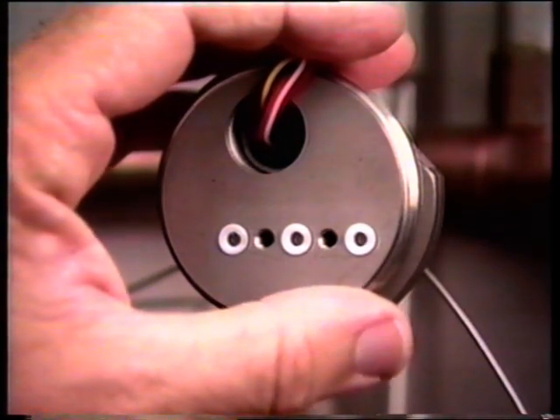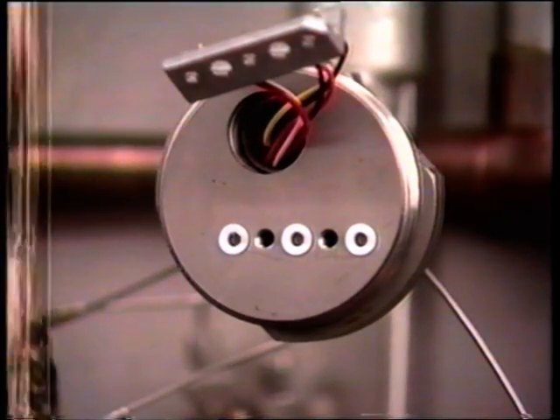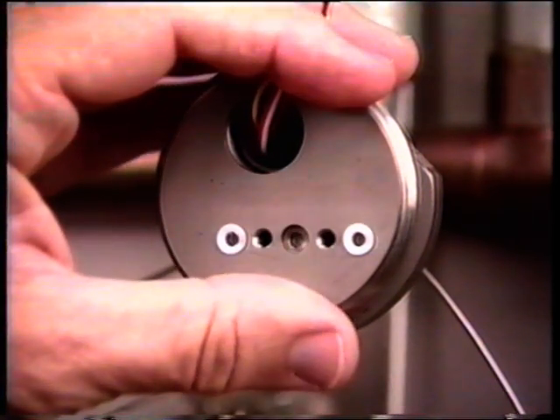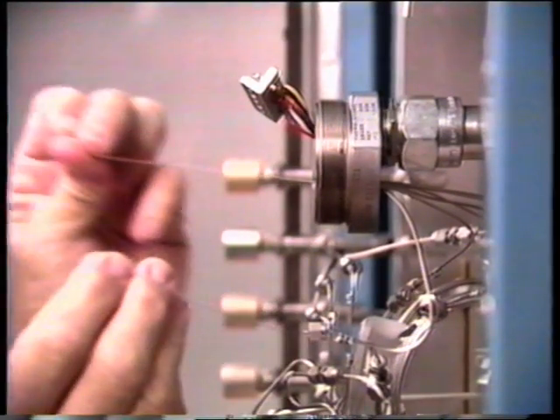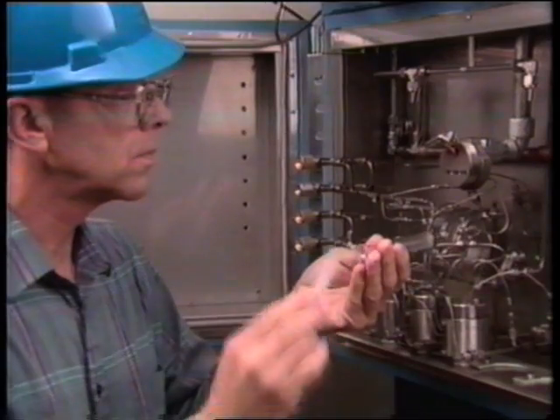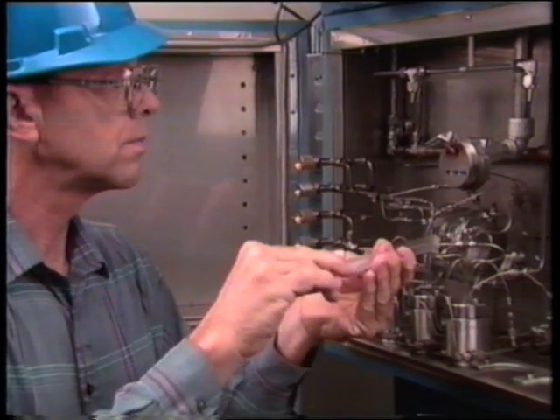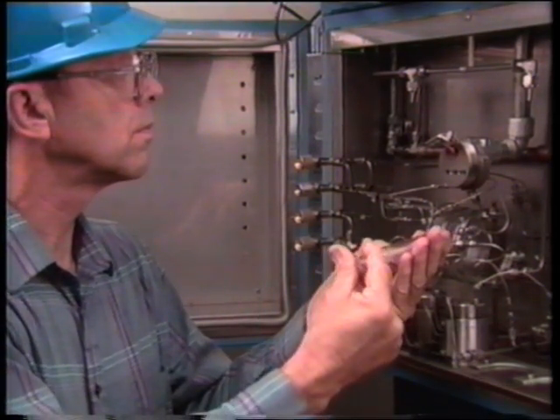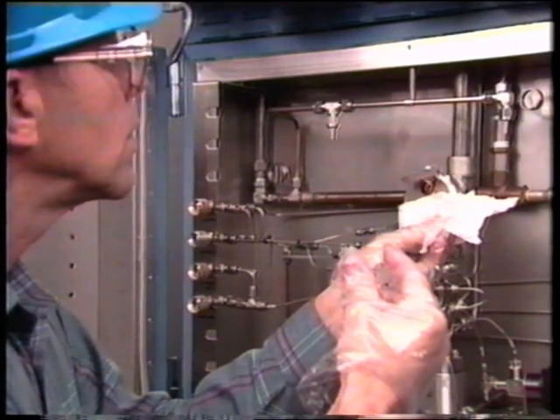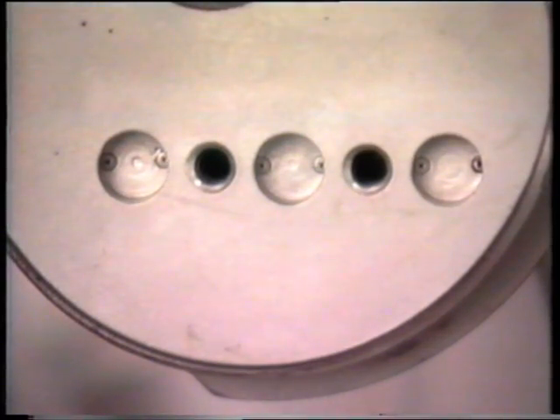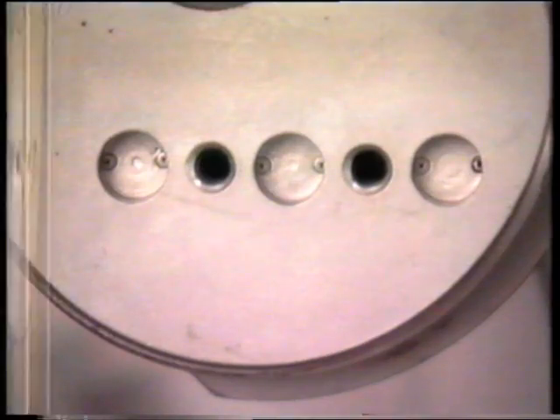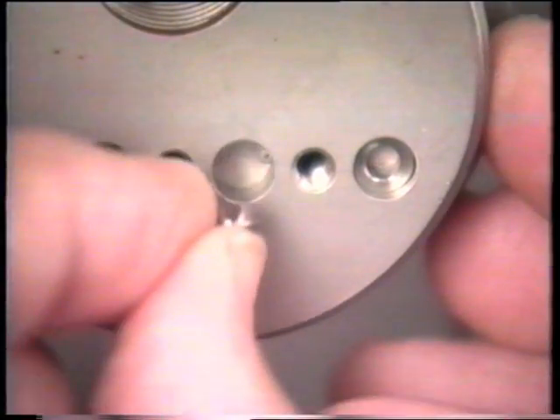To do this, remove the thermistors as just described. Remove the Teflon bushings and metal inserts. Run a wire through the detector tubing. Use a syringe to force air through the tube to blow out any loose debris or dirt. Then clean it out with solvent. Verify that the thermistor cavities are clean and dry. Install the metal inserts and position them so that the slots in the bottom are perpendicular to the line of cavities. This allows the sample and carrier gas to flow completely around the thermistor.